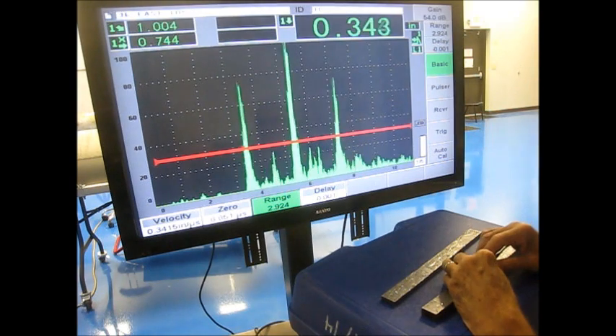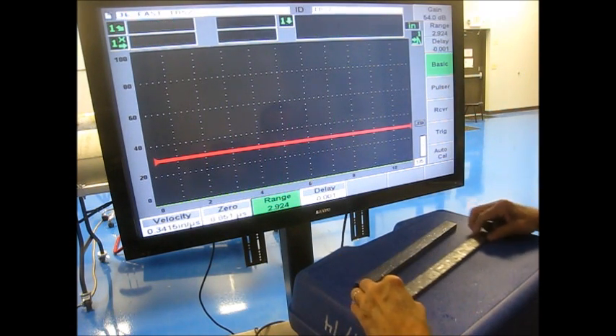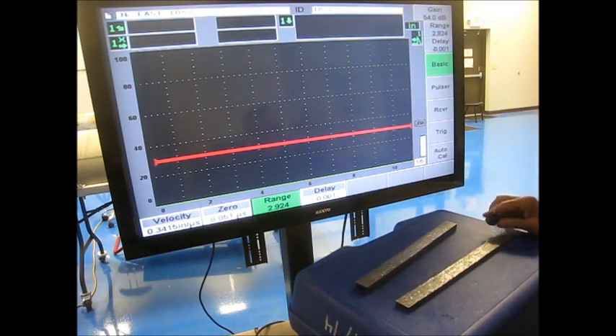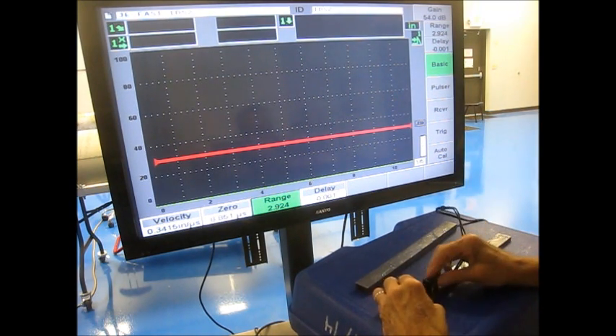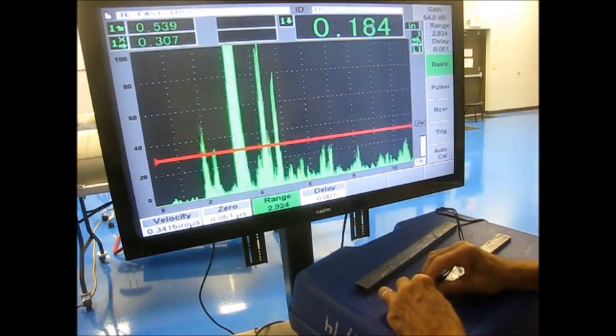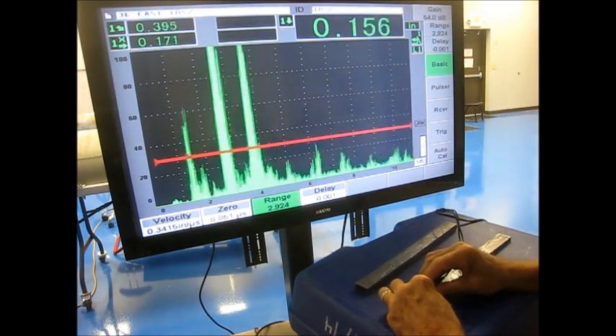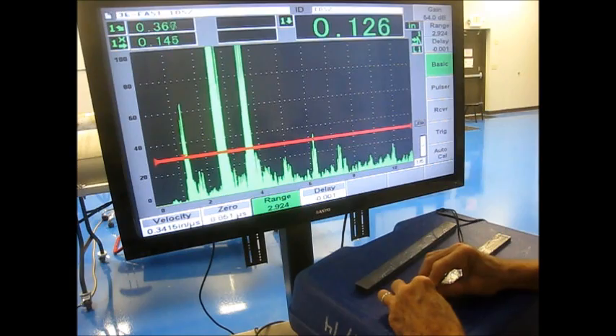And if I try to do ID sizing on the notches, I've got the notches down. I'm going to go to the 210 notch. The depth of that tip is 90. And where I peak that up is not too far off from 90.